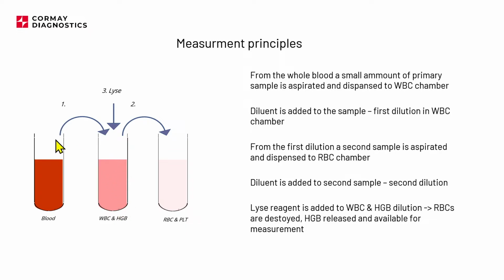Since we basically took 20 microliters of blood and diluted it by, I don't know, some factor of 200 or something, the number of red blood cells is still very high. So what we need to do for RBC analysis is dilute the sample one more time. This second dilution for RBC PLT is by a factor of a few thousand, because the analyzer is taking 20 microliters of pre-diluted blood from the first chamber and then transferring it to the RBC chamber. And this is the second dilution for RBC PLT.